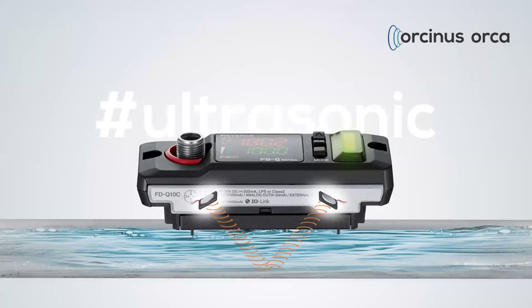This picture shows you why we are maintenance free. The biggest advantage is that it is a contactless measuring, which means the quality of your cooling water, by the way, it's also possible to use the system with cooling oil, is not affecting the sensor because it's not touching it.